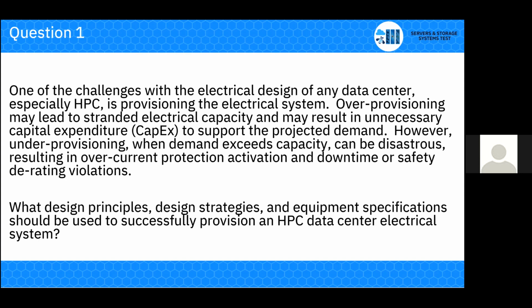And how the power is going to flow through the system. Specifically with cycling, a lot of data centers are just tested to full load capacity. This new thing we're working on with fluctuating power levels isn't typically tested in a standard facility commissioning program, so we try to mimic the actions of the load to make sure we wring out all the problems before the supercomputer is installed.